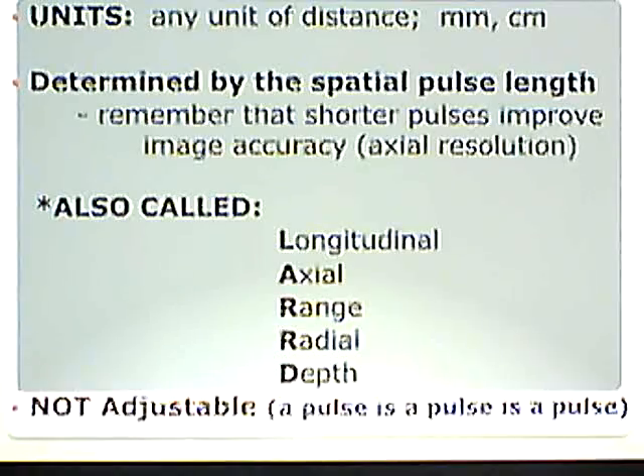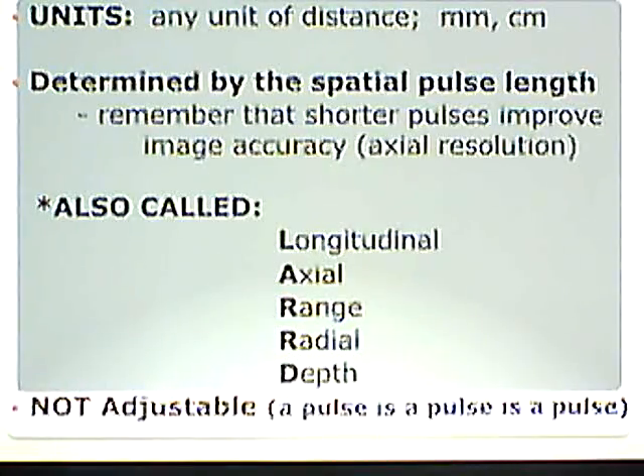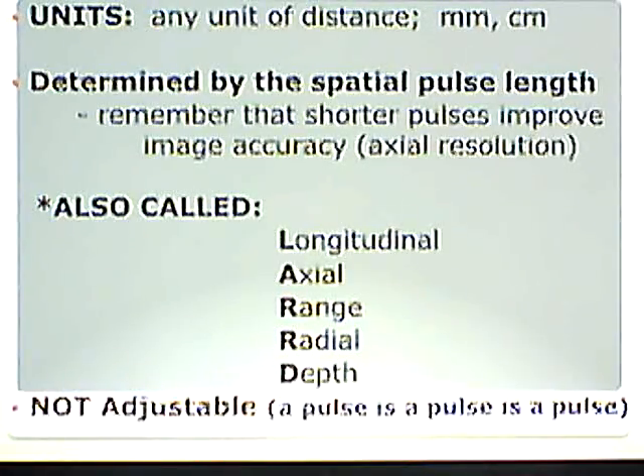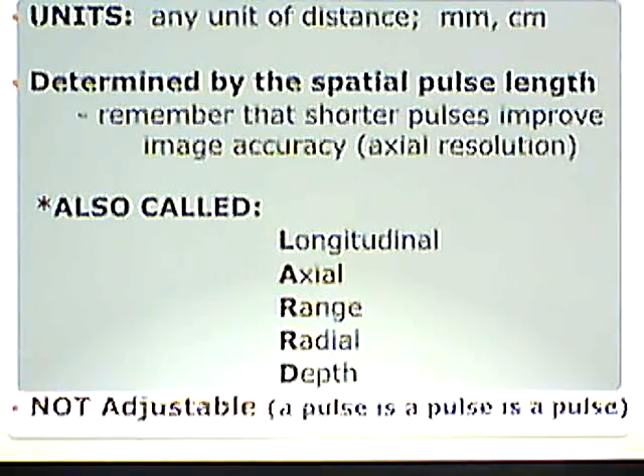The units for axial resolution are a distance — millimeters, centimeters — because it is that minimum distance two structures can be from each other and still be seen as two separate objects. It is determined by the spatial pulse length. Remember, we talked about how shorter pulses improve image accuracy, so it makes sense that spatial pulse length determines axial resolution.